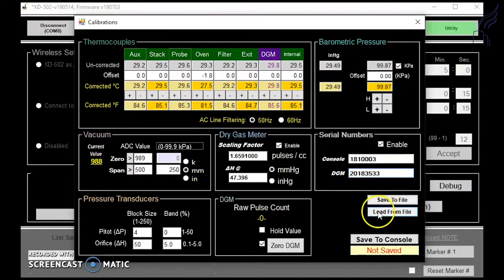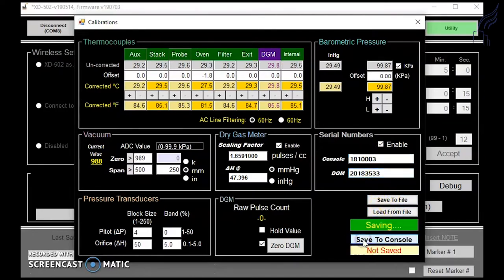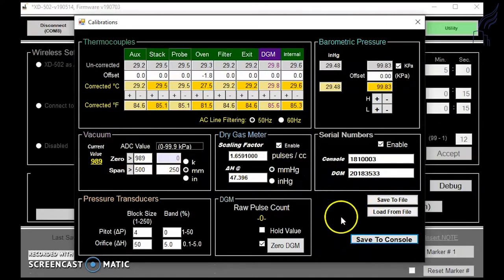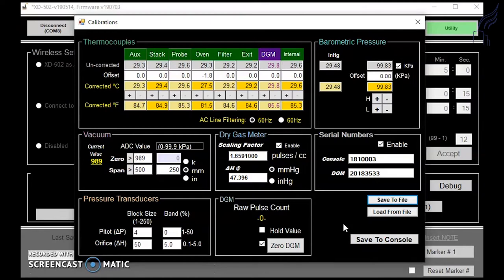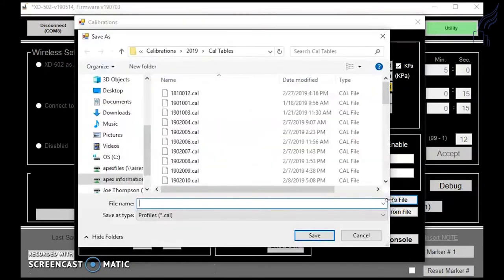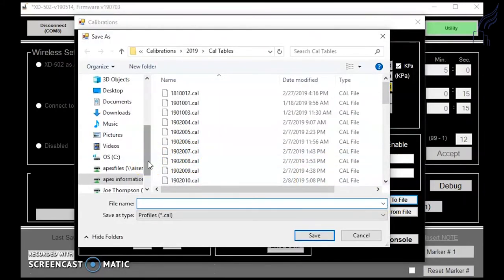Once you're satisfied with all the data, you can click save to console to save all this information to the console itself. It's always recommended to save your calibration data to a separate file. So if you click on the save to file tab, it will allow you to save your calibration data to your computer or to a separate hard drive.